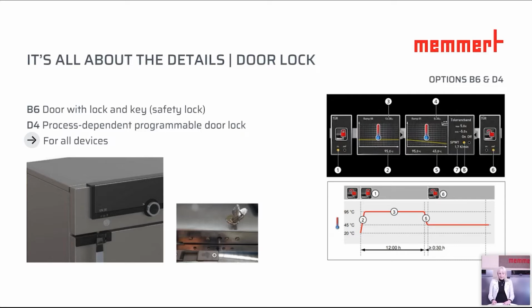It is also possible, if you are not using the Atmo control software, with the timer function on the display. That means whenever you start the timer function, for example, you set 50 minutes and then it starts, it counts downwards. Whenever it starts, the door is locked. And only after the process of, for example, these 50 minutes, the door can then be opened. Let's go further.